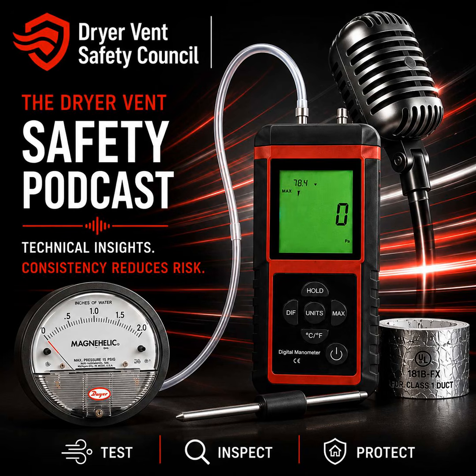And finally, red, restricted airflow, 12 pascals or lower. That is a severe restriction. The vacuum has collapsed, and it absolutely must be cleaned. Those numbers, 12 or below for red, 13 to 24 for yellow, 25 or above for green, are the finalized criteria of the DVSC publication. They let a tech quickly and confidently classify the system's condition.